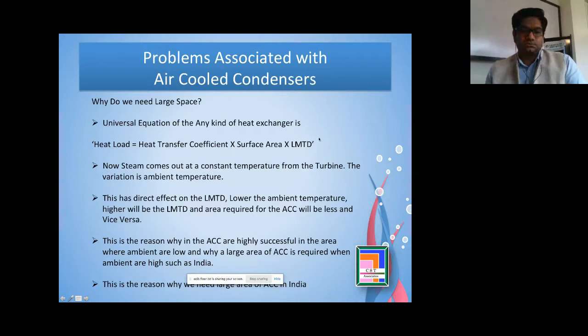So let's say the temperature goes to 45 or 50 degrees centigrade. At that time, LMTD becomes lower. Lower means there is a demand for more surface area, but this is already fixed. So we have an option of increasing the air volume. Even if we increase the air volume and we are still not able to cater to that kind of heat load, the only option left is to reduce the steam from the IGV valve. And once that steam is reduced, the heat load comes down. Once the heat load comes down, it matches the surface area, and it gives you a balance of plant.